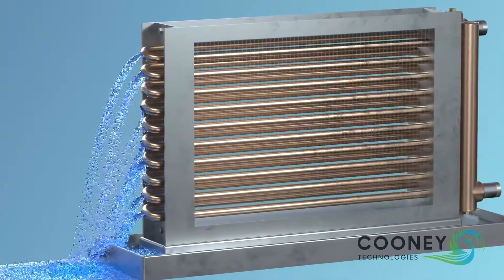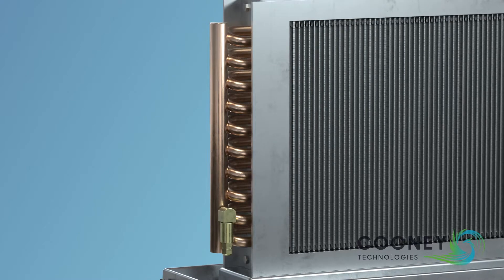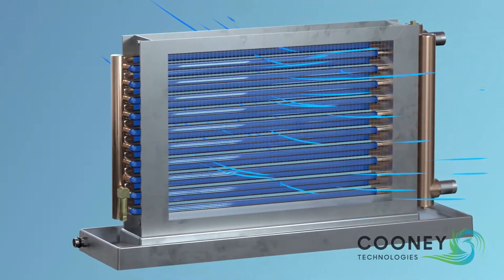Now, let's look at the same freezing scenario from before, but this time with Cooney Freeze Block Technology installed on the coil. Cooney Freeze Block Coils use expansion relief headers, which are attached to every return bend and mated to a Freeze Block relief valve.